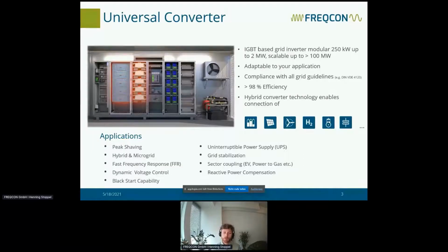That means you don't need a converter. For example, your PV system is producing DC voltage, and your battery system is working with DC. In a traditional setup, you have to convert the PV energy from DC to AC, and before you store it in the battery storage, you have to convert it again from AC to DC. With our solution, we directly combine both technologies in one DC link, meaning you have no losses from AC-DC conversion.